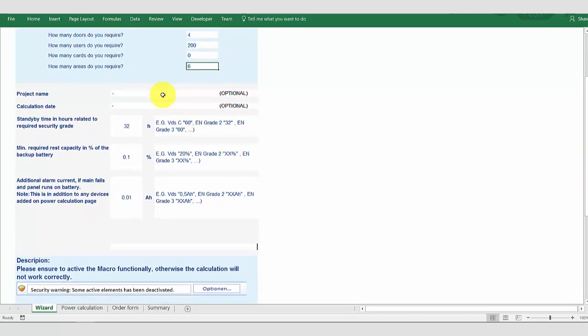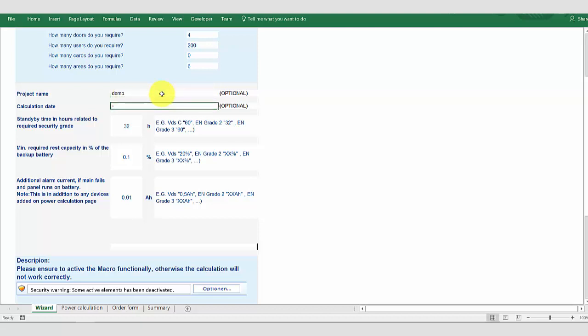You may also optionally add a project name. This is purely for organization and serves no function in the system. You should take care of selecting the standby time. For EN systems please select 32 hours, for grade 3 60 hours, and for VDS Class C systems 60 hours.